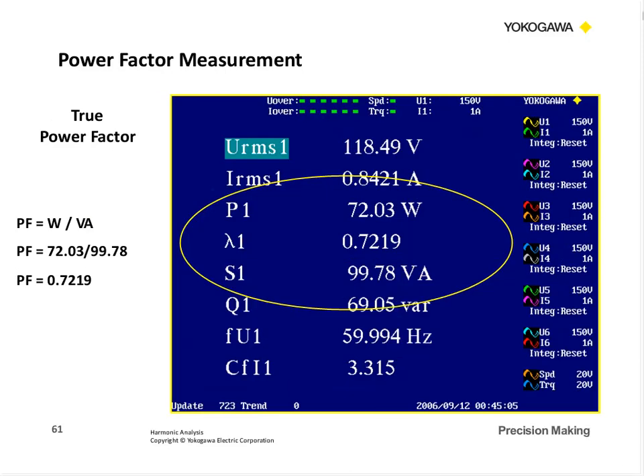So here's our power factor measurement again, and I'll make sure we understand this. We do a true power factor measurement of watts divided by VA. So here's our watts, 72.03. Here's our VA, 99.78. So it's the watts divided by the VA that gives us the 0.7219 as our power factor.